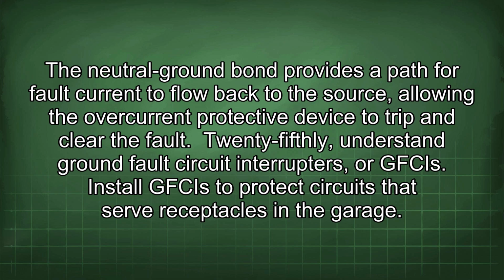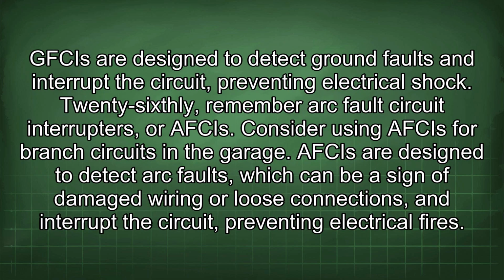25thly, understand ground fault circuit interrupters, or GFCIs. Install GFCIs to protect circuits that serve receptacles in the garage. GFCIs are designed to detect ground faults and interrupt the circuit, preventing electrical shock. 26thly, remember arc fault circuit interrupters, or AFCIs. Consider using AFCIs for branch circuits in the garage. AFCIs are designed to detect arc faults, which can be a sign of damaged wiring or loose connections, and interrupt the circuit, preventing electrical fires.